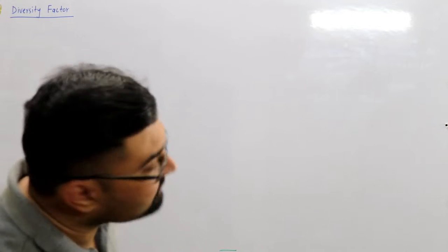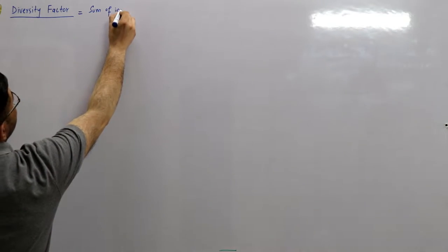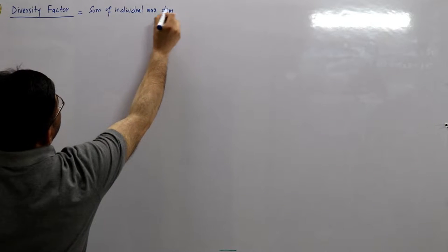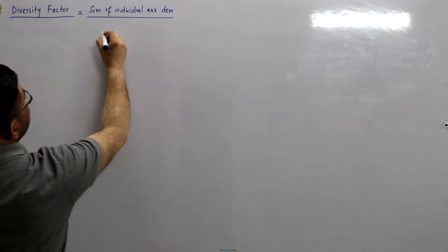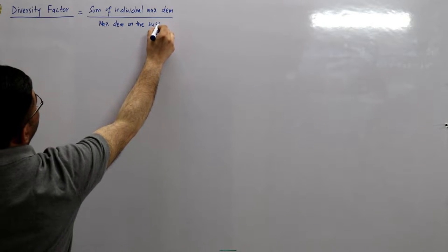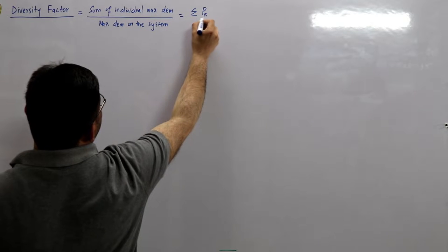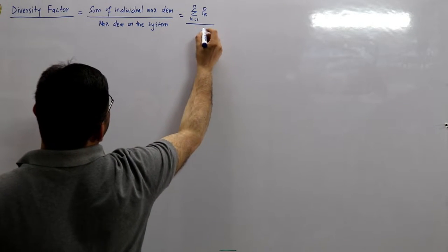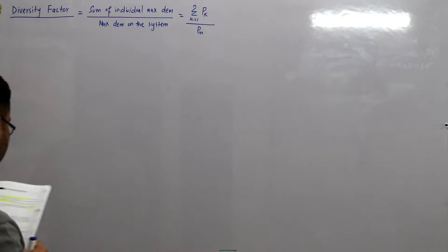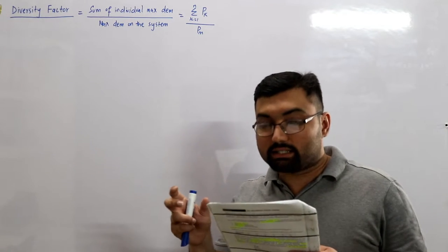If I define it: the diversity factor is the summation of individual maximum demands divided by the maximum demand on the power system. Writing it as a formula: summation of Pk for k running from 1 to n, for n number of consumers, divided by Pm of the system. The habit and trend followed by various consumers is referred to as diversity, and it is determined by the diversity factor.